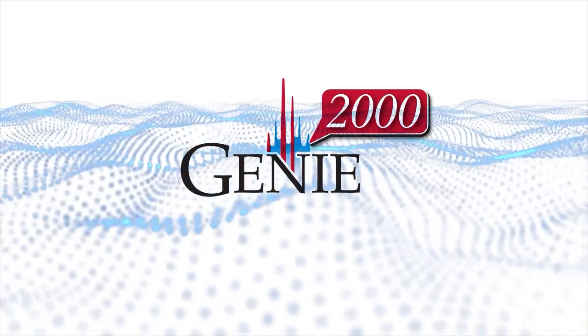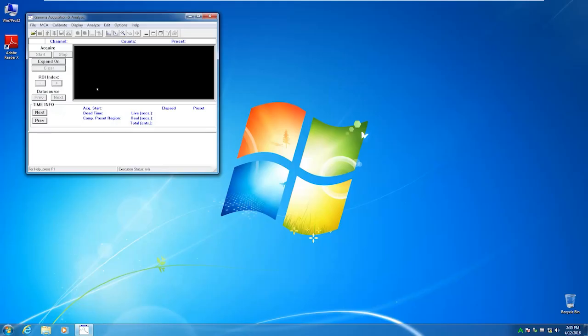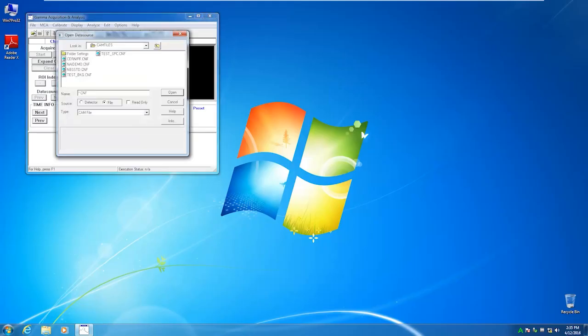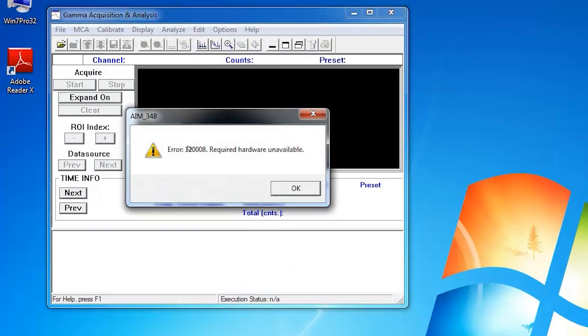When you install Genie 2000 software on your computer, it does not automatically install all of the drivers needed to communicate with various multi-channel analyzers Mirion offers. If you see the following message when you try to open a detector using Genie acquisition and analysis software, and you are using an older MCA like a DSA 2000 or AIM modules, then you will probably need to install the Snap Protocol driver on your network card.